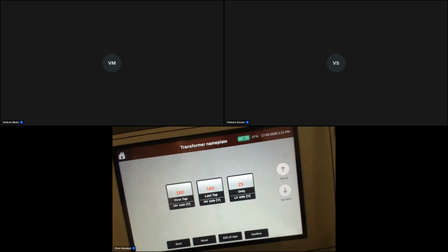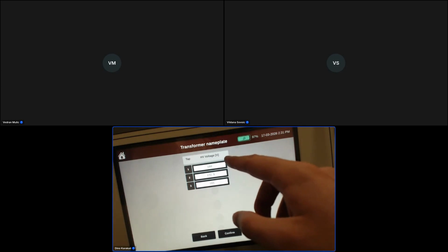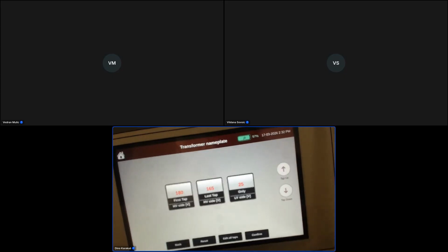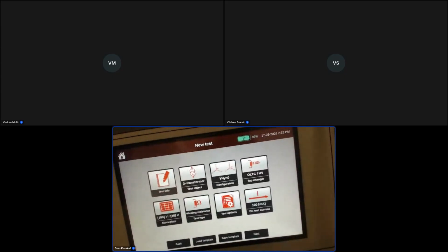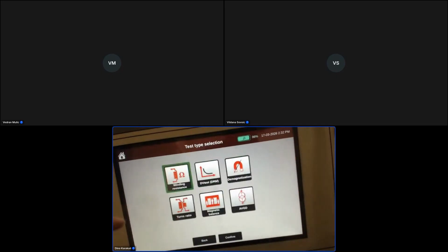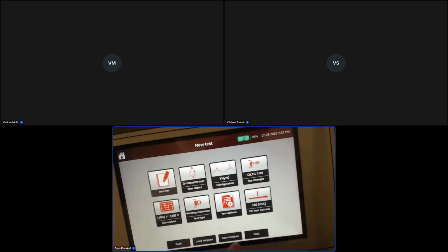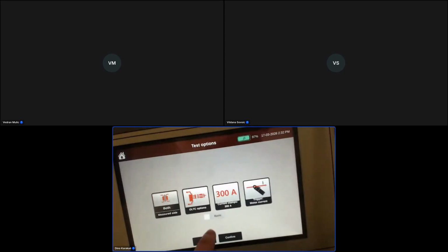Okay, we can edit all the taps. If we do not, our device will recognize the values between the first and last step. But if you, for some reason, want to change the value on some of the positions, you can do it manually. But we are happy with this because there are only 3 tap positions and it is okay. So we press confirm. We select the test. We want to perform winding resistance measurement. For now, press confirm. We go through test options.